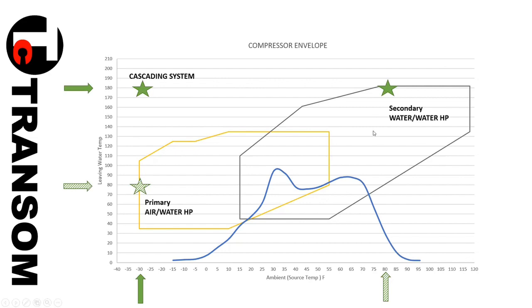And what effect does that have on your COP? I've tried a number of different ones. You take this ratio, we can bring this further down and this one further up. It's almost like you take the same pressure ratio and ask how you divide it. Do you put it 50-50 or 60-40? For all the ones I did, the COP only changed very slightly, within 2-3%. It wasn't a very big jump. I was a little surprised myself. I would have figured that the closer you were to 50-50, the more beneficial it would be. And it was, but only so much, so it doesn't drop off that much. So it's more about what the range of your systems is and what you want to do with it.